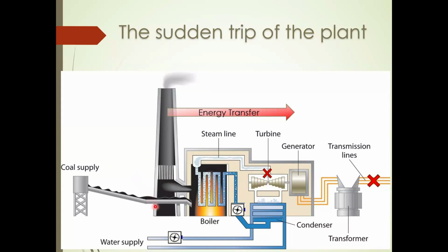Of course, even though you stop the coal supply here, some residual energy will remain in the furnace and of course in the steam line. So when you close the steam turbine governor valves, this line will get overpressurized, or else sometimes all the steam lines need to be dumped into the condenser. So what you do is, this happens almost automatically.